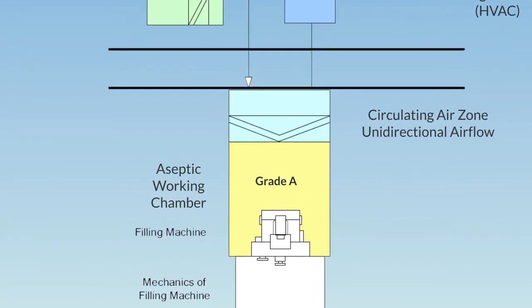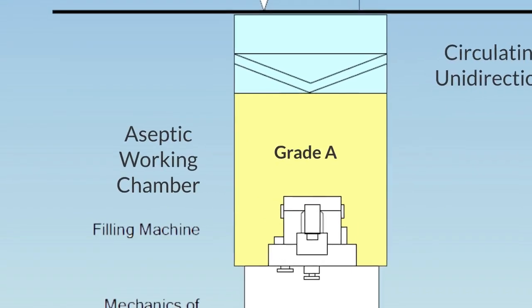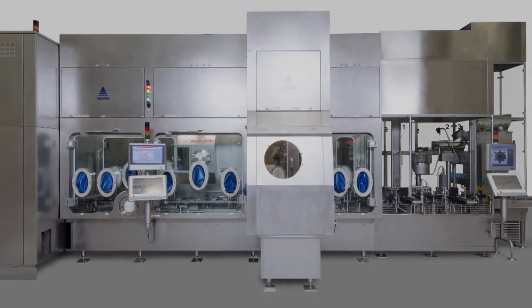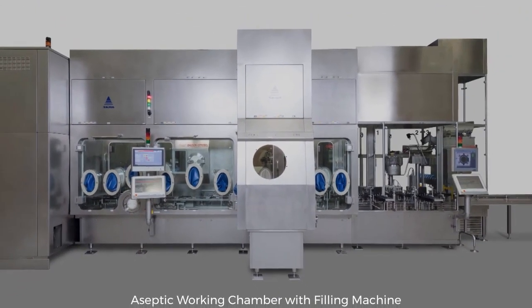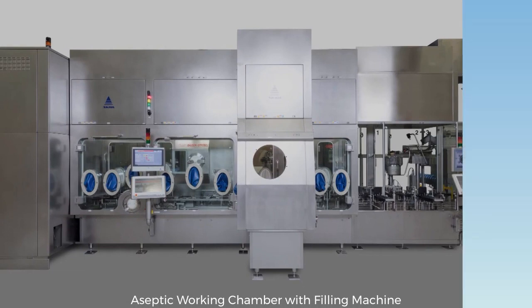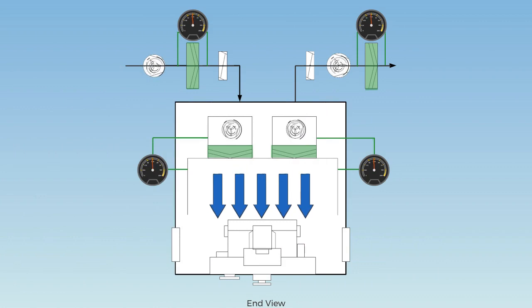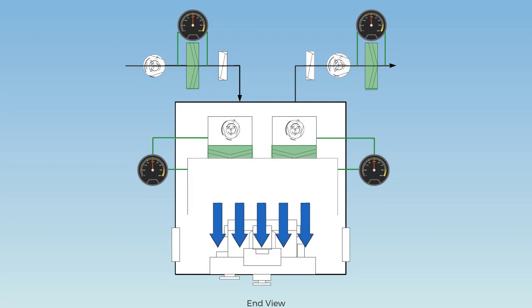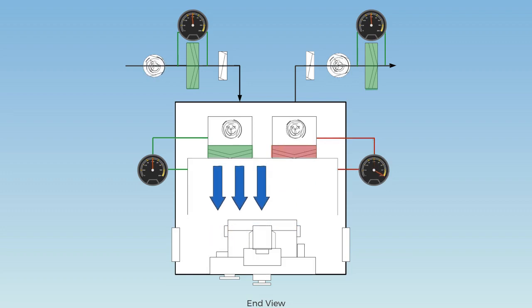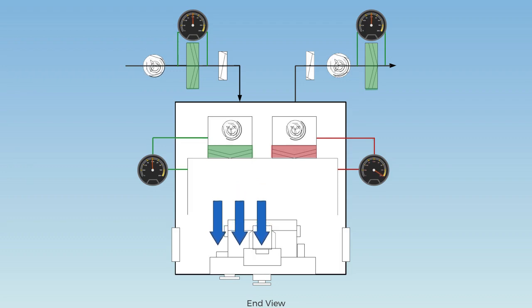As we've already learned, the isolator must provide a GMP Grade A environment for the filling machine. This is accomplished by flowing constant and optimized HEPA-filtered air over the filling machine and product that are completely enclosed within the isolator. To maintain this constant, clean airflow, the HEPA filters are measured on each side of the filter by differential pressure sensors. If the differential pressure of a HEPA filter exceeds a predefined value, this is an indication that the filter is blocked and needs to be replaced. An alarm will be shown on the HMI if the value is too high.